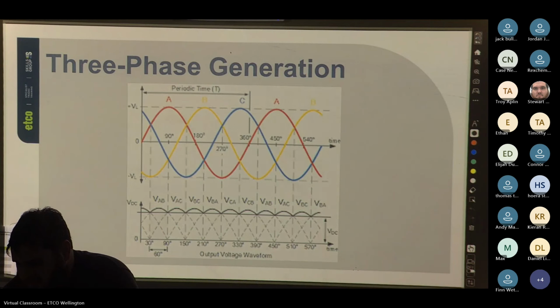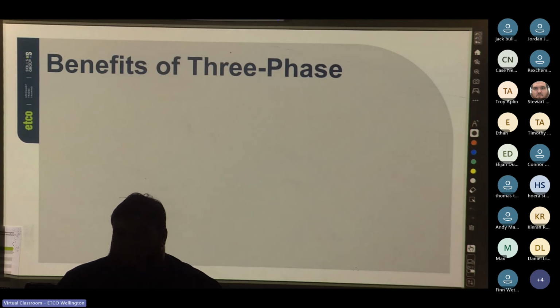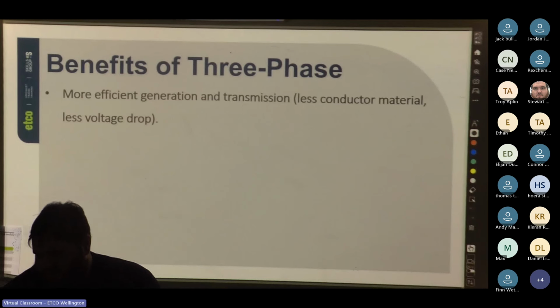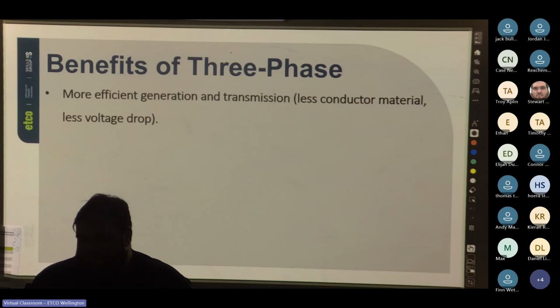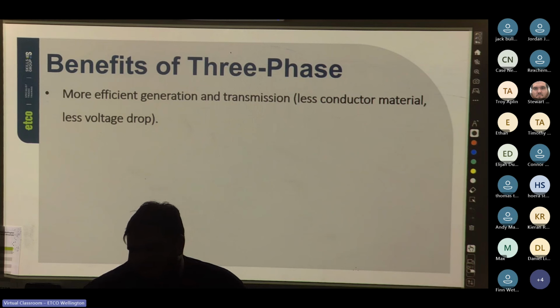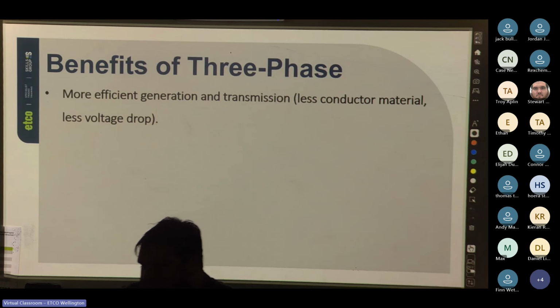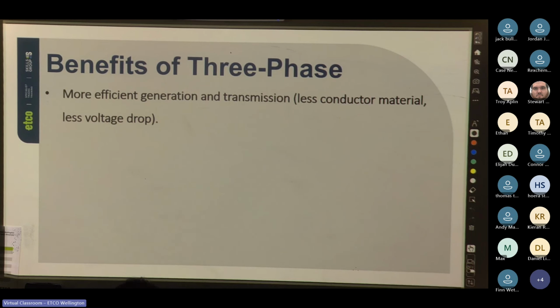Cool. Cool. So some of the benefits for three-phase. So we've got more efficient transmission and generation, so less conductor material and less volt drop. So because we've stepped up the voltage to 400 volts, we've decreased the current. So therefore, we're getting less loss and less volt drop, because as we looked at last week, volt drop is dependent on amps per meter. So how many amps?